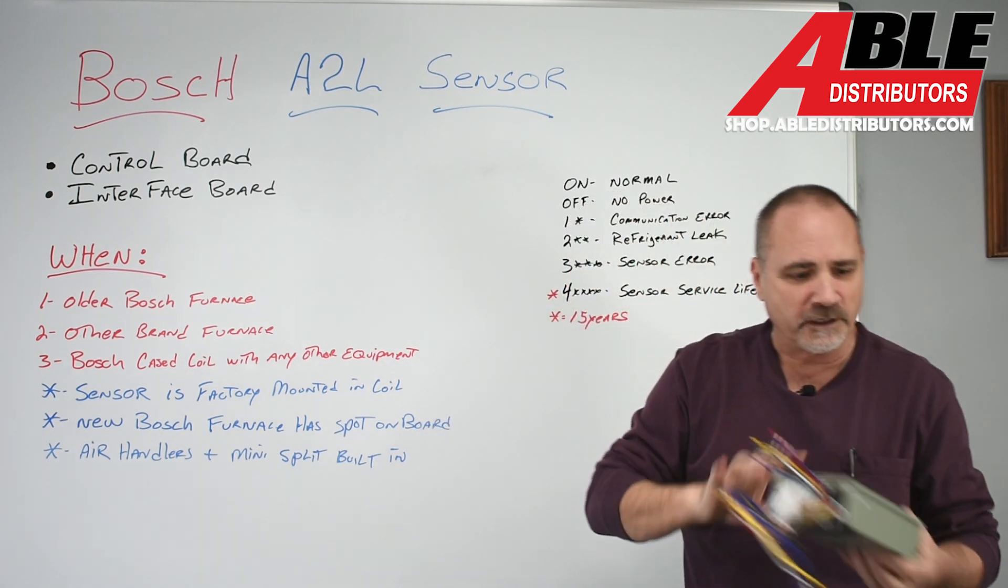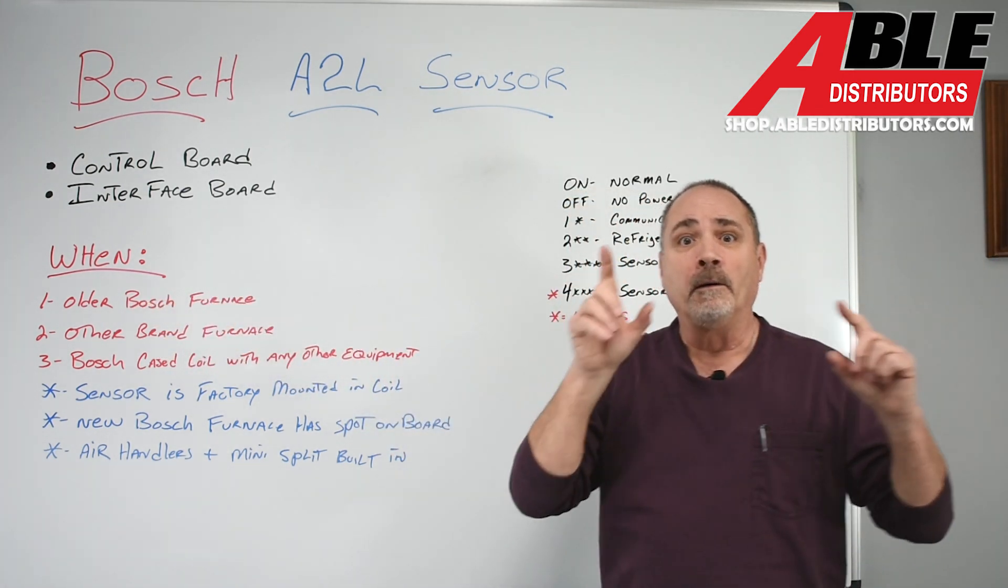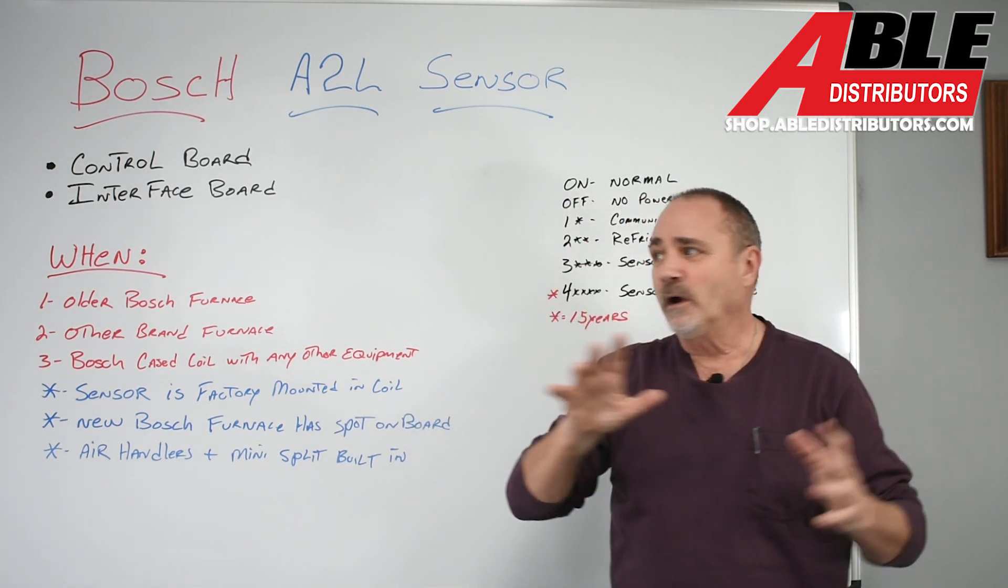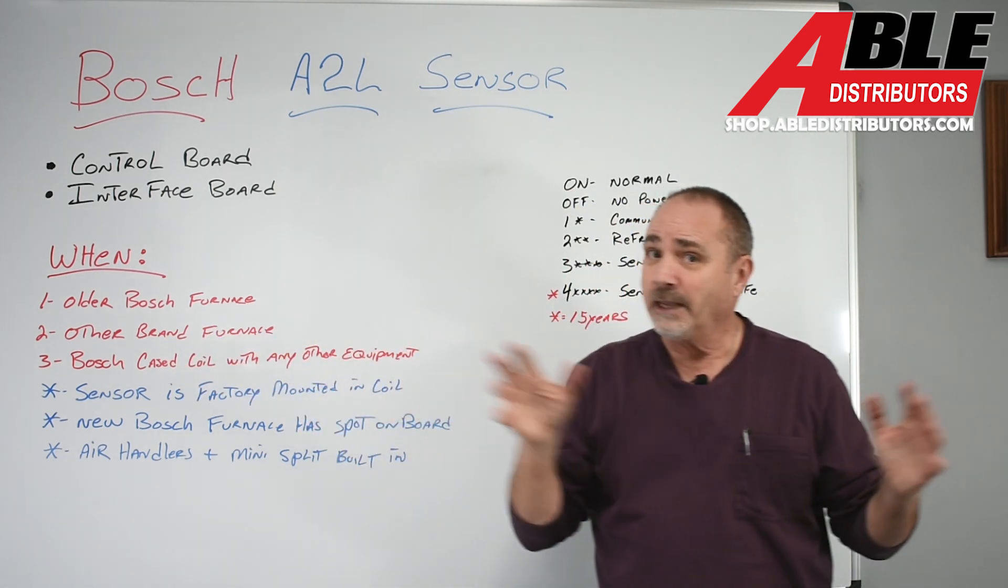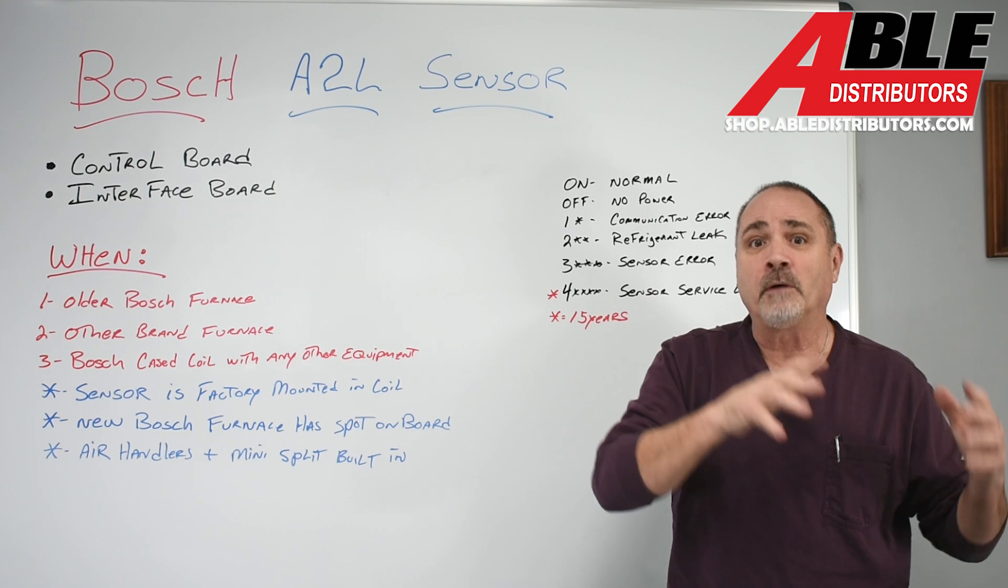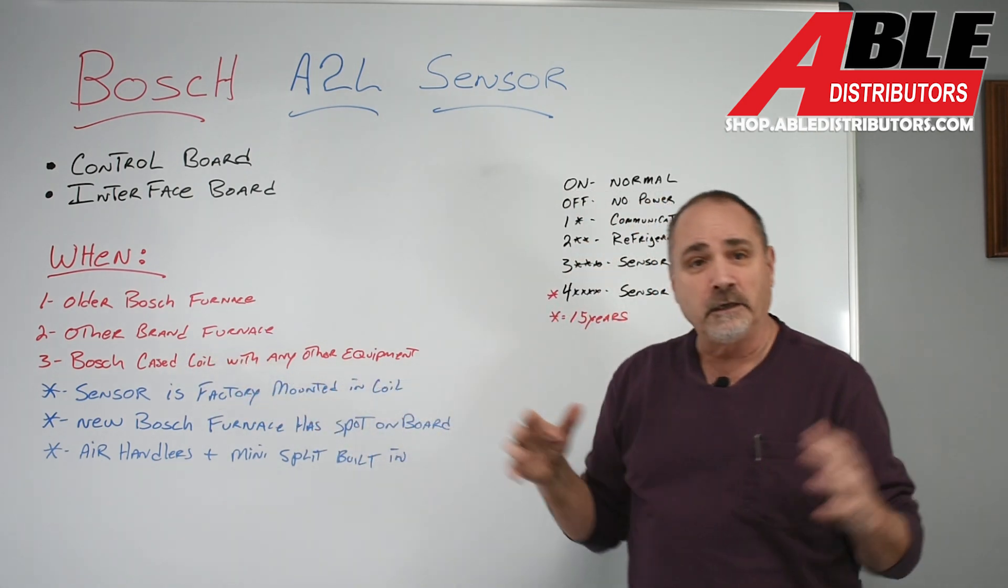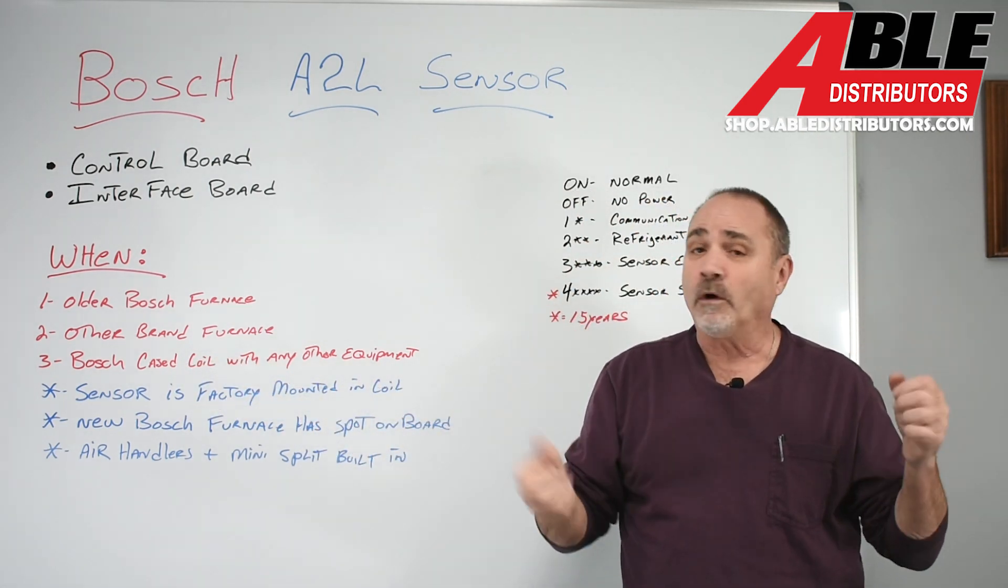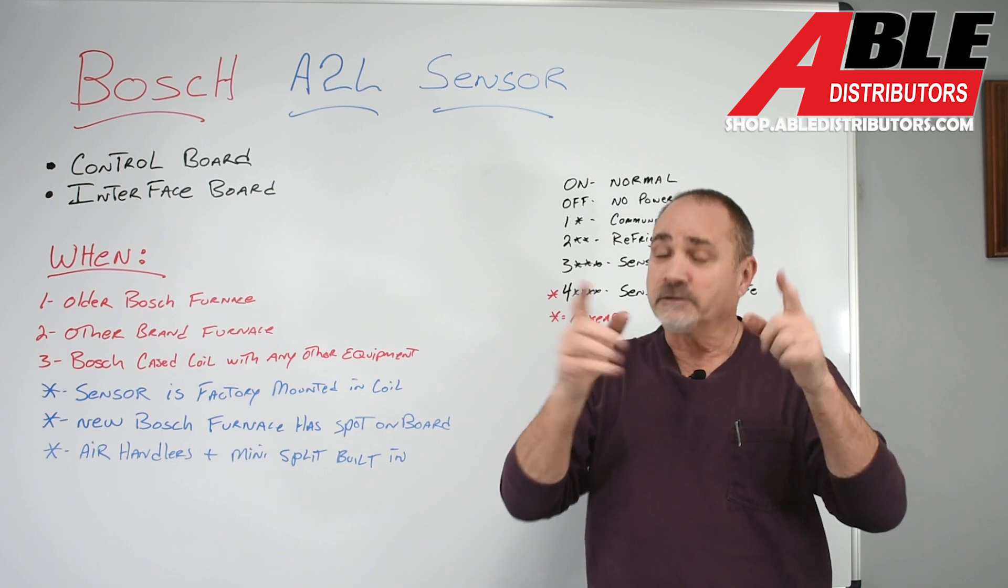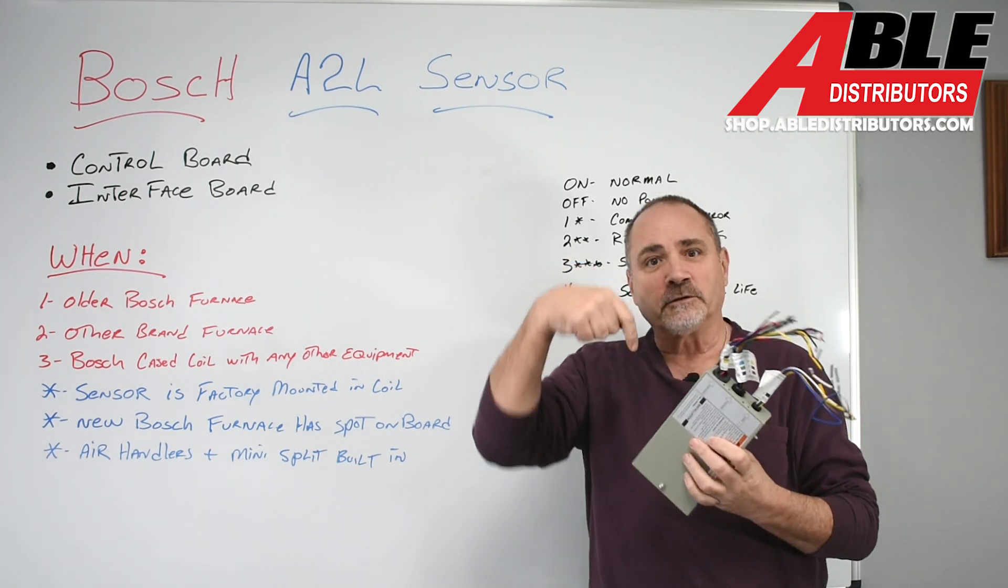This box, this interface board, you're going to need it when you put a new 454 A2L Bosch heat pump with an older Bosch furnace. That could happen a lot. If you put their cased coil and a Bosch heat pump with any other brand of furnace, and again, that could happen a lot because it's a great piece of equipment, and you might not need to replace the furnace every single time you want to put a heat pump or a really, really good AC on that furnace. Anytime you use the Bosch cased coil with any other piece of equipment, essentially, they have a really, really nice cased coil. The sensor comes built in.